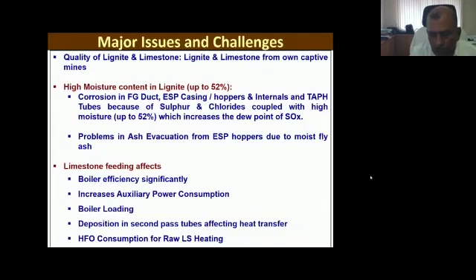Whenever we take up ESP maintenance work, we have to do partial loading, which causes huge impact to overall plant availability and plant load factor. During plant outage, for refurbishment of the fields and restoration of damaged fields, we need almost 30 to 40 days, and sometimes we have to go for another 2-3 months to comply with SPM requirements. So we have to run the unit on part load with one ESP pass, which is a huge cost.